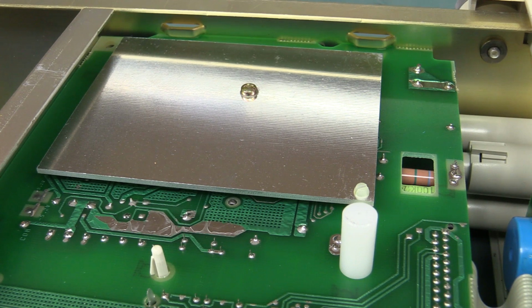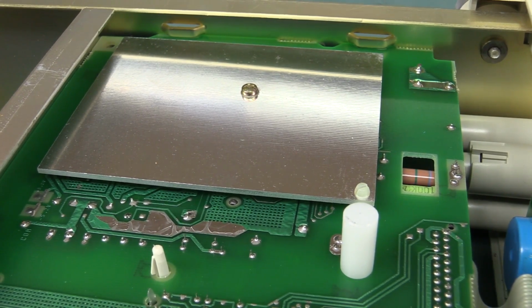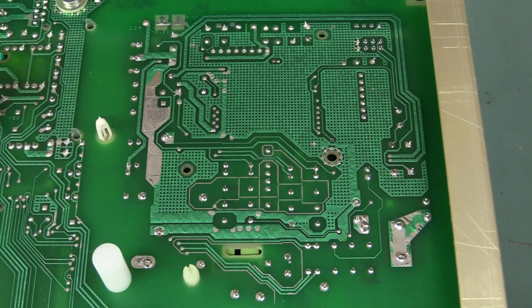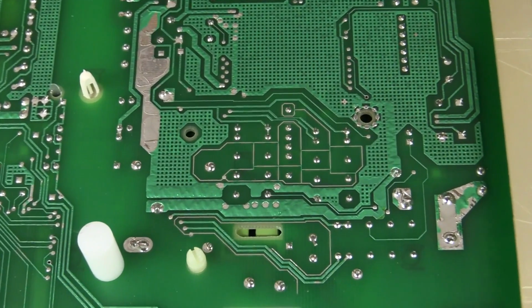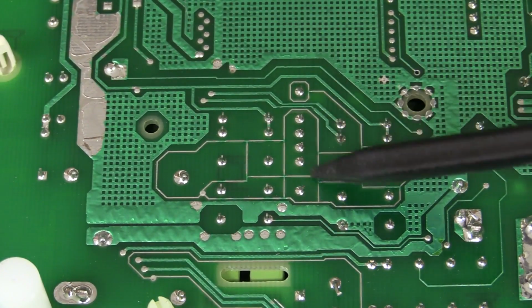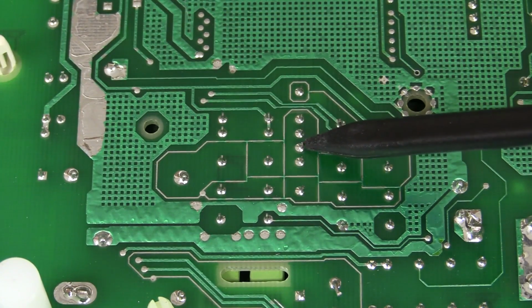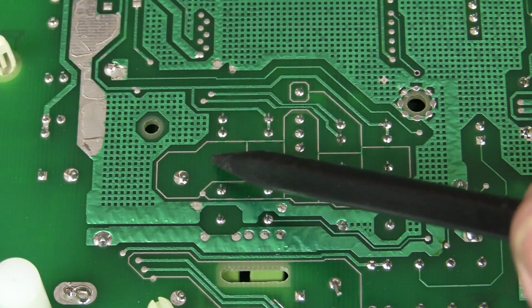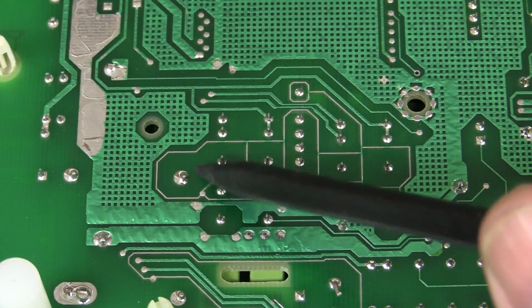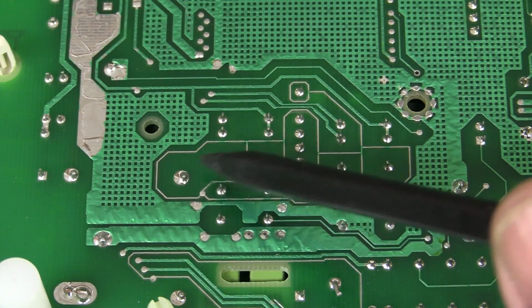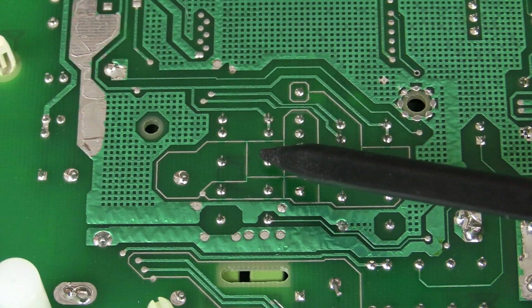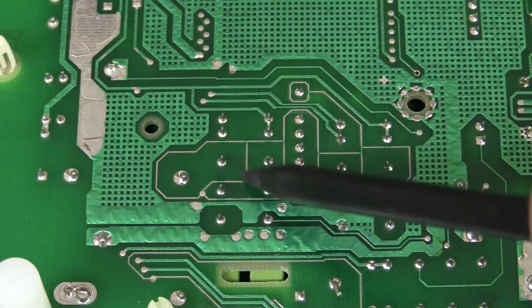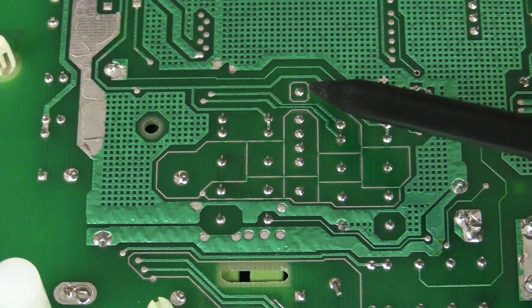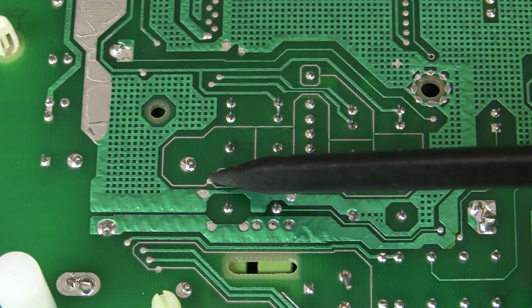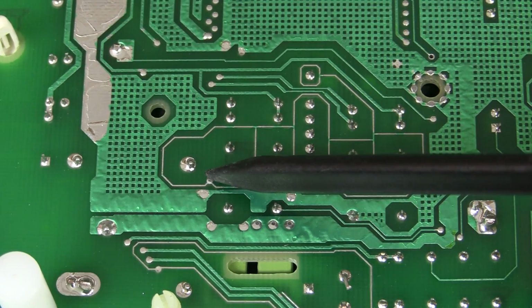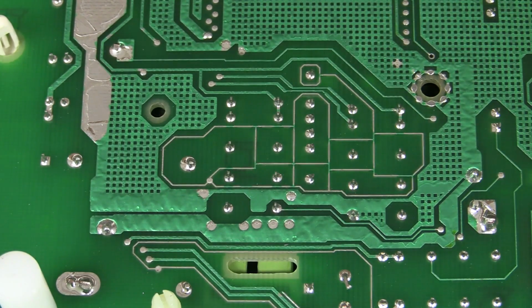And we've got a shielding plate on the bottom, so we'll whip that off. As you saw, we had a conductive shielded box on the top side. It's mostly shield on here, but what you really notice are the guard rings. Check them out. I've explained guard rings before. There we go, crisscrossing in there, designed to stop leakage between individual nodes. They obviously don't care about leakage between these two nodes, i.e. if you're getting any contaminant or condensation on the board between those two terminals, it doesn't matter. But it certainly matters if it's between that one and that one there. So they put a guard ring around that, and that's kept to a common circuit level, and they're all connected back to that common via down there. That would be a ground reference guard point as part of the analog to digital converter circuit.